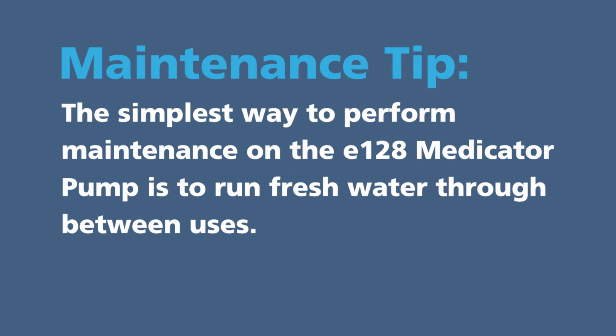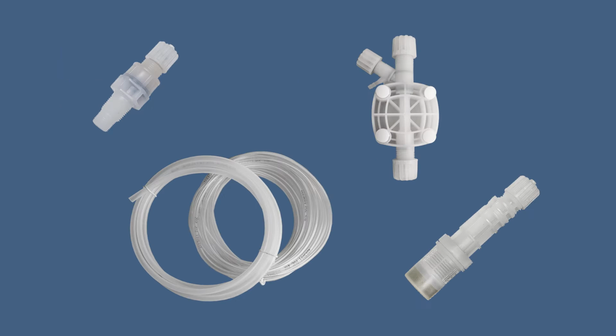The simplest way to perform maintenance on the E128 Medicator pump is to run fresh water through between uses. This helps to prevent buildup inside the foot filter, tubing, pump head, and injection valve, and allows for these components to last longer. Pump head.